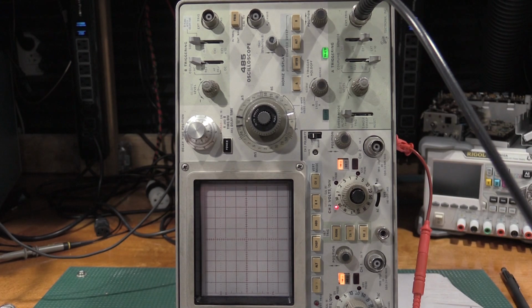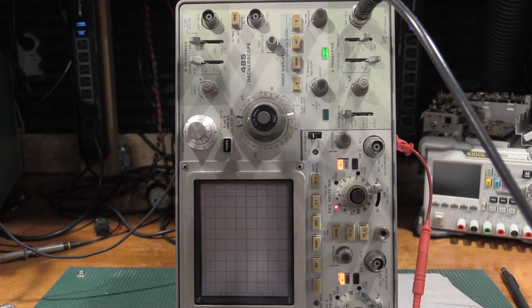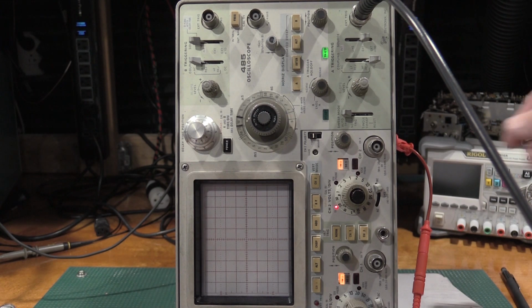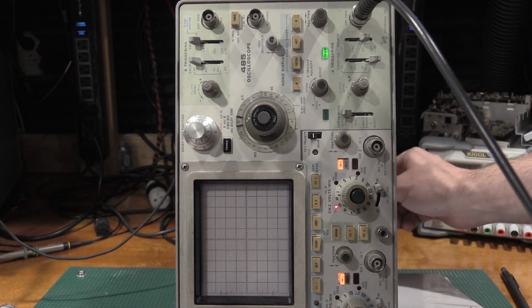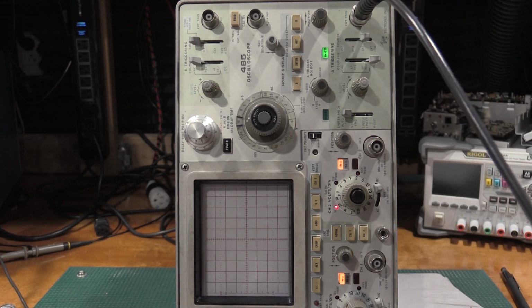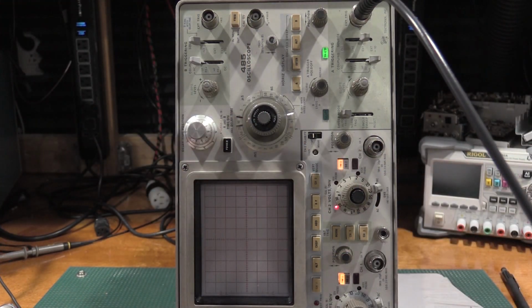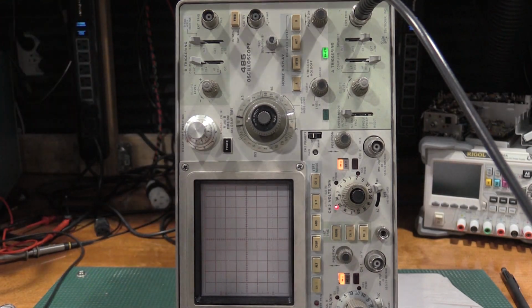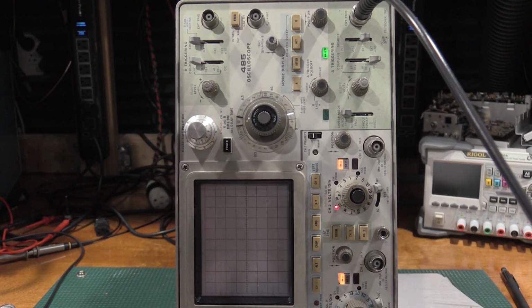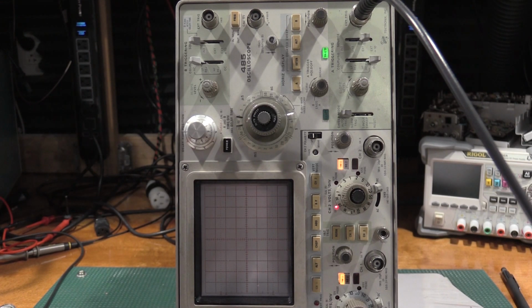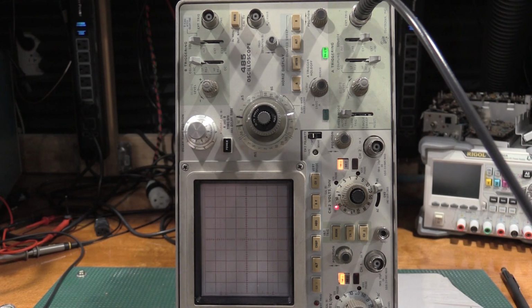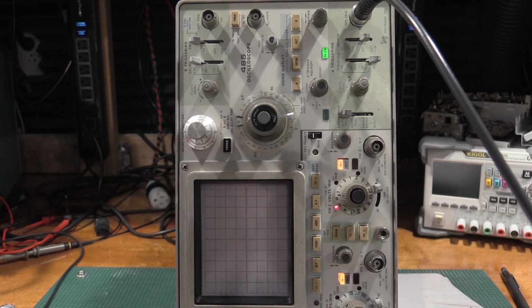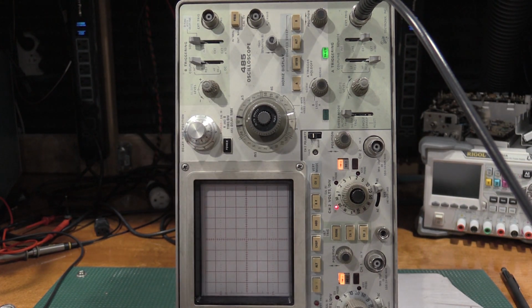Okay, I'm going to run the B triggers through a testing procedure. I don't think the B triggers need much. I didn't get the feeling that they were causing me problems during calibrations, so I'm going to check the centering and a few other things, and also check the low level triggering. I'll do some highlights on camera, but I'm going to just run through it real quick just to validate them. If they're validated, I'm not going to adjust the potentiometers. I don't need to. The A trigger was fighting me like crazy on this thing, so definitely needed an adjustment there.